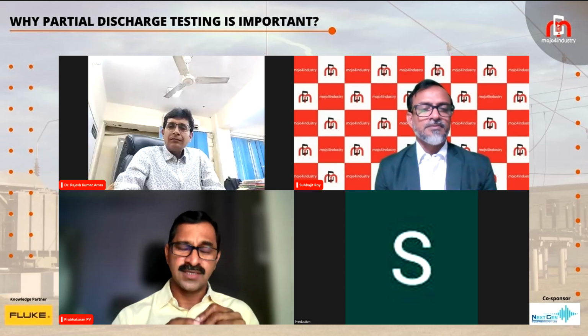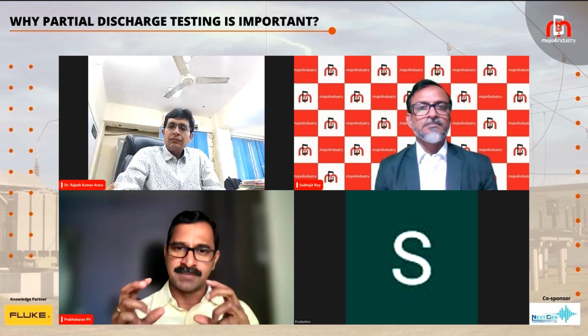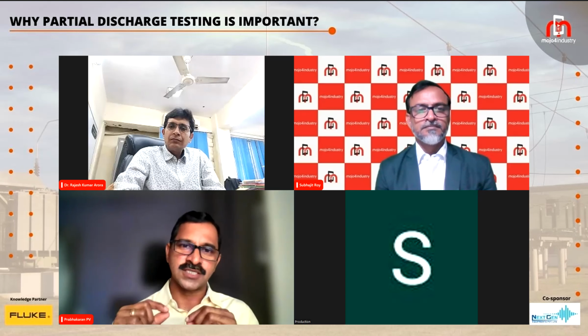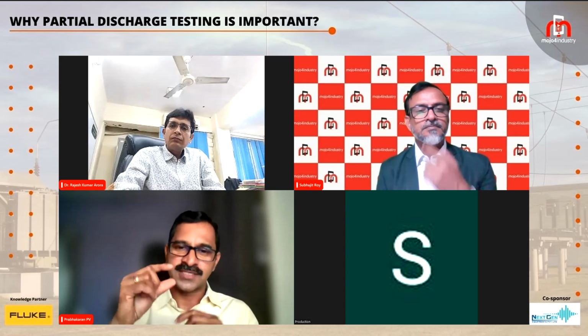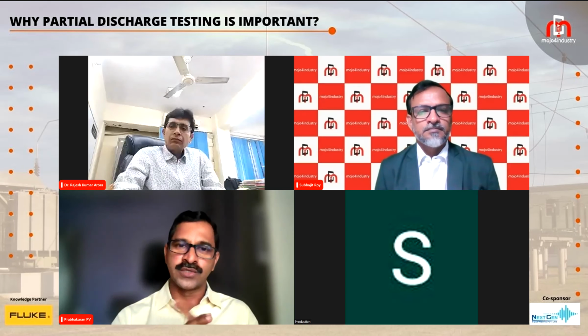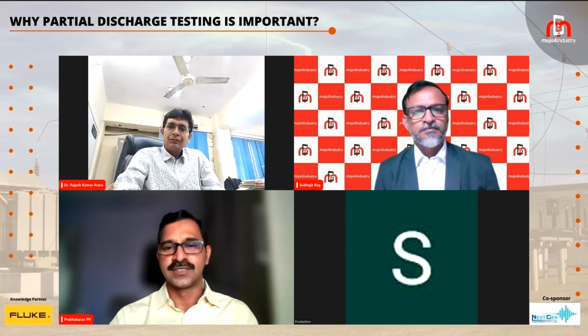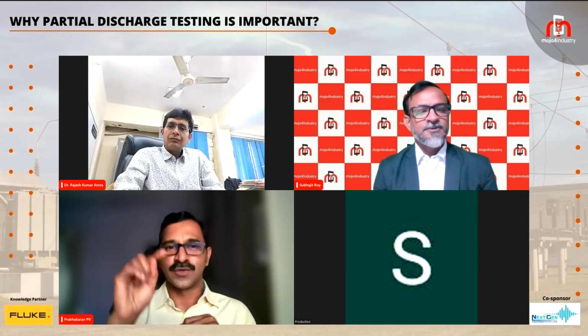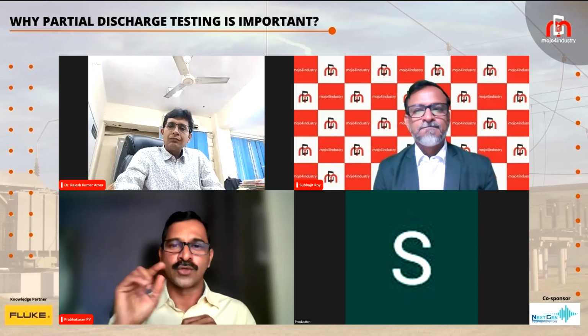I would like to add there are methods in our camera, because the frequency of partial discharge is unique, and the noise you're going to get is in a different frequency range. That's why you can select and avoid other frequencies - that's another method in our instrument we adopt. Every noise, every acoustic frequency is different, so you can select that bandwidth and get the right kind of thing - you can point or zero down on the actual frequency of interest.